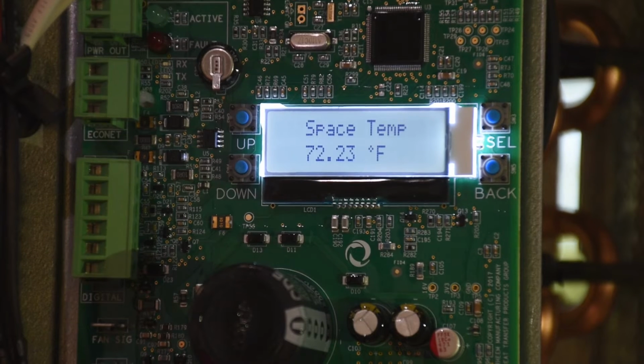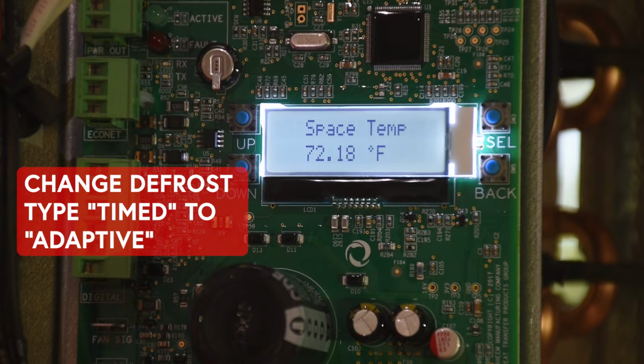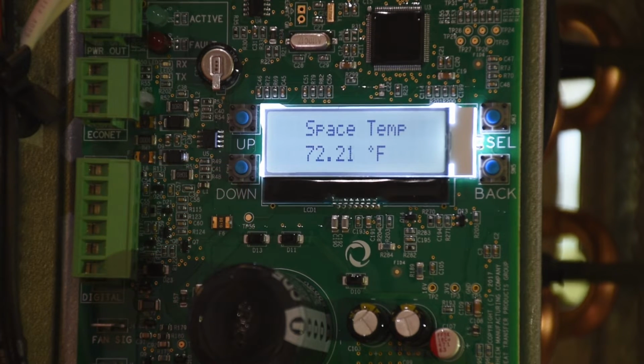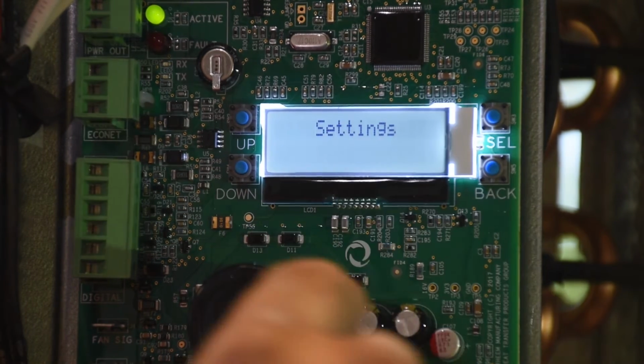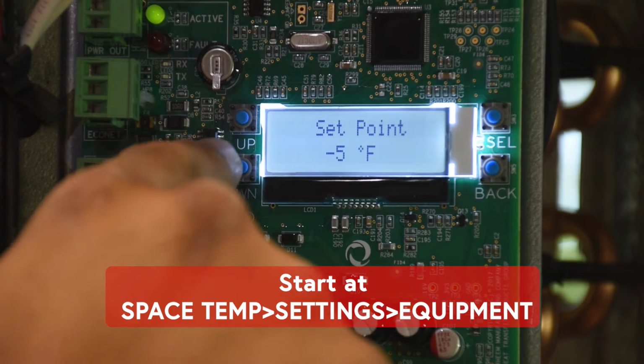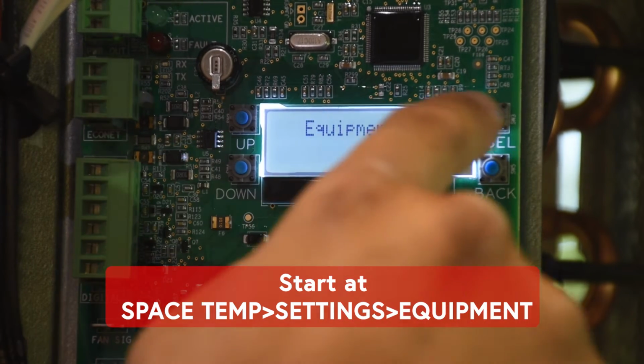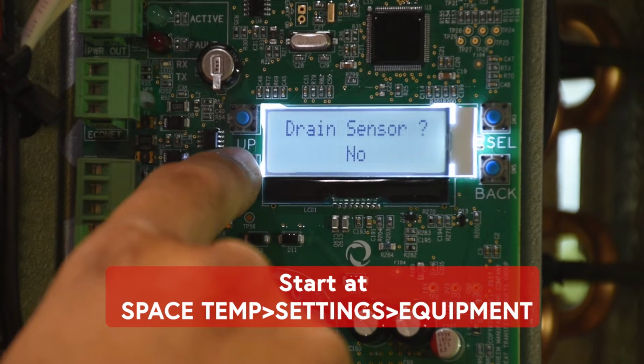To adjust the defrost type of the controller between timed defrost or adaptive defrost, go to the settings, hit select to go to the settings submenu, hit select again, then scroll down to equipment, and then scroll down to look for the defrost type configurable setting.